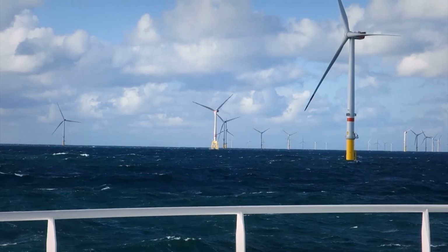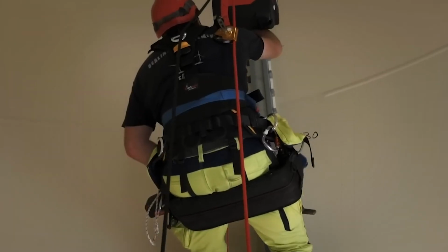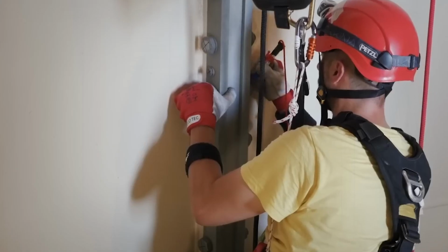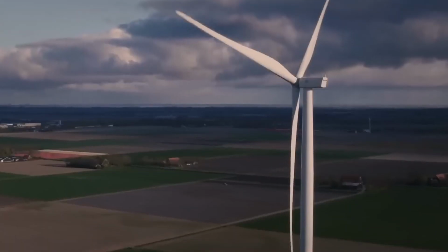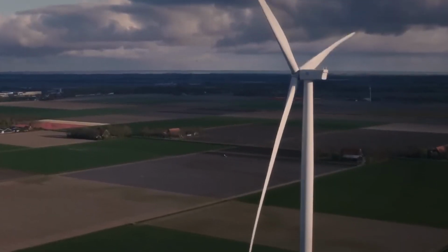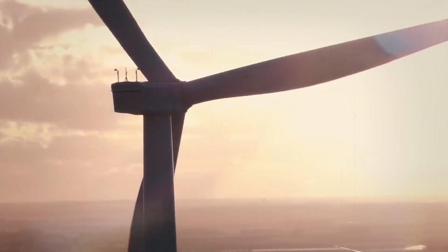Perform a tap test on the device. It is an indication of separation if a part generates a hollow sound. Utilize thermal imaging techniques. There is a difference in the way that delaminated portions absorb and release heat compared to unbroken parts. Conduct a thorough assessment of any suspect areas during each and every scheduled inspection, particularly following storms.